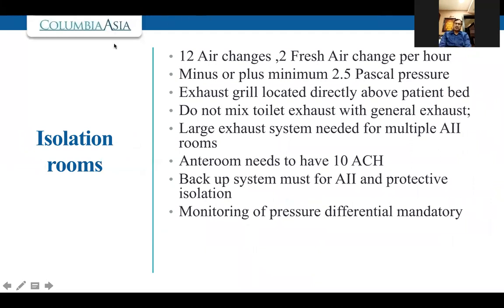Another important aspect is isolation rooms. Generally, people have a lot of misunderstandings about this, especially negative isolation rooms and positive isolation rooms. These are the two most important isolation rooms which we have. The standard isolation room doesn't require anything apart from a closed door and a change of gear for the healthcare worker. So 12 air changes is what is recommended by all the guidelines, whether it is critical care guidelines or ASHRAE guidelines or various other national guidelines. 2 fresh air changes are permitted in this. No need to have full complete fresh air changes. So minus 2.5 or plus 2.5. If it is a positive pressure room, then plus 2.5 is the minimum requirement.